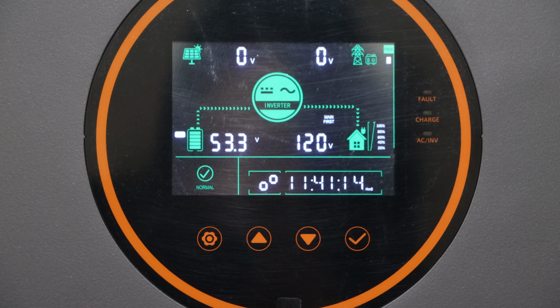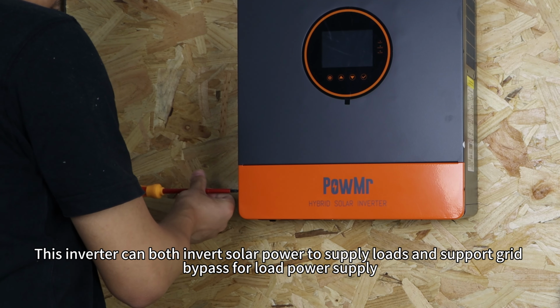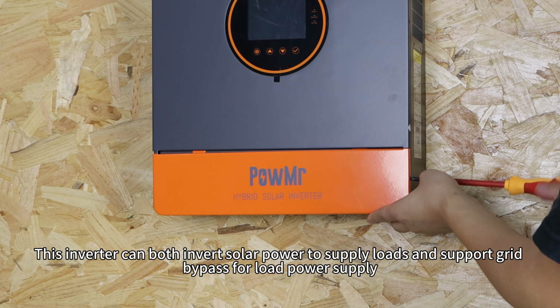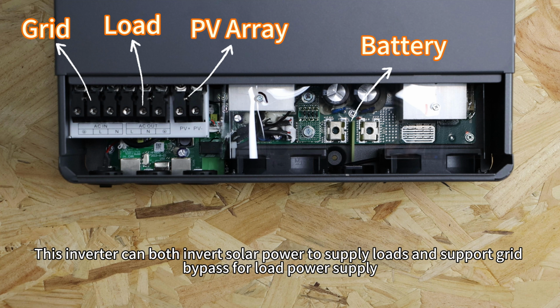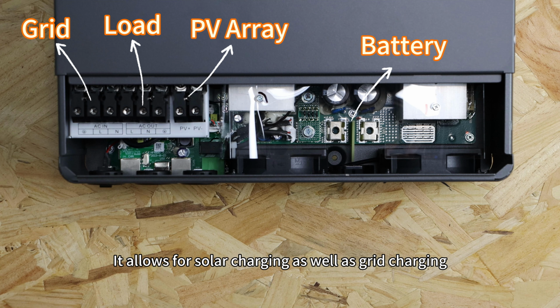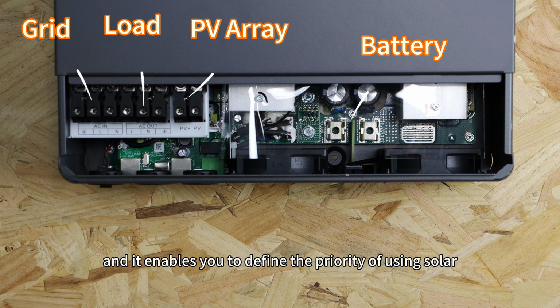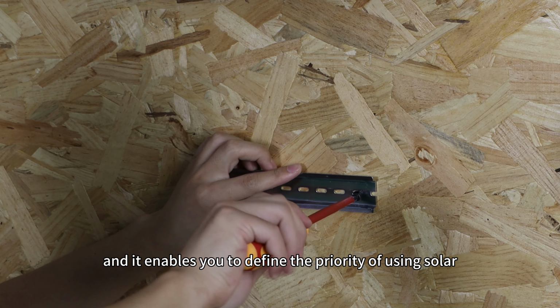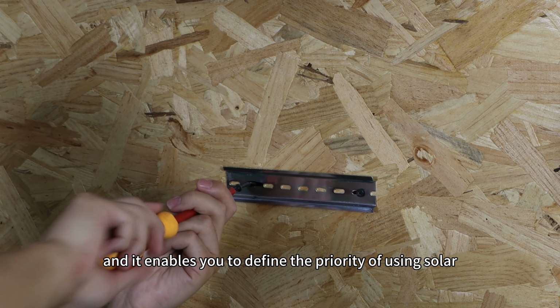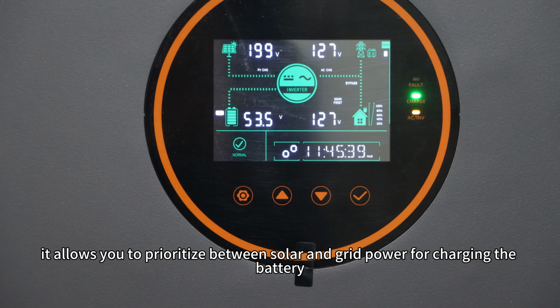The 5 kW system utilizes a PowMr SP5K all-in-one solar inverter. This inverter can both invert solar power to supply loads and support grid bypass for loads power supply. It allows for solar charging as well as grid charging, and it enables you to define the priority of using solar, grid, and battery power to supply loads, based on your needs and specific usage scenarios. Additionally, it allows you to prioritize between solar and grid power for charging the battery.